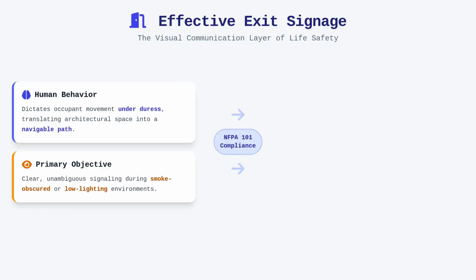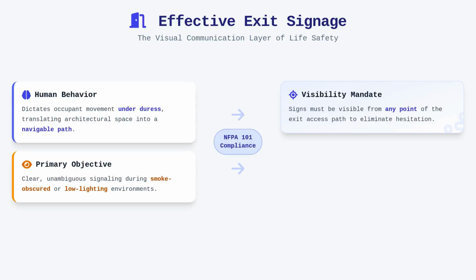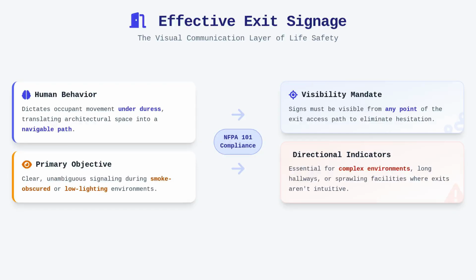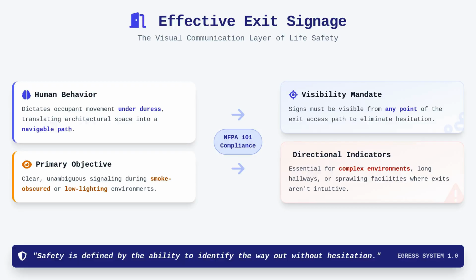Codes like NFPA 101 prioritize visibility, requiring that signs be positioned so they are visible from any point of the exit access path. This implies that if an occupant is standing anywhere within a corridor, they should be able to identify the direction towards safety without hesitation. If a clear line of sight to an exit is obstructed, directional indicators must be provided to guide the flow of movement. This is particularly relevant in complex environments with long hallways or sprawling facilities where exits may not be immediately intuitive.